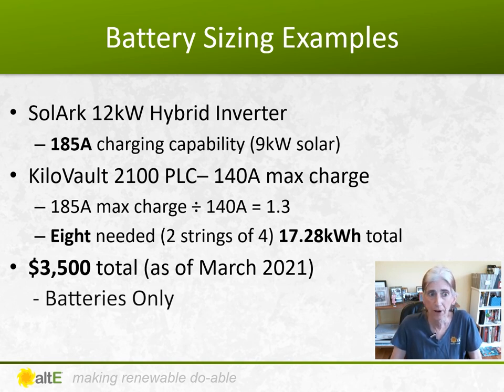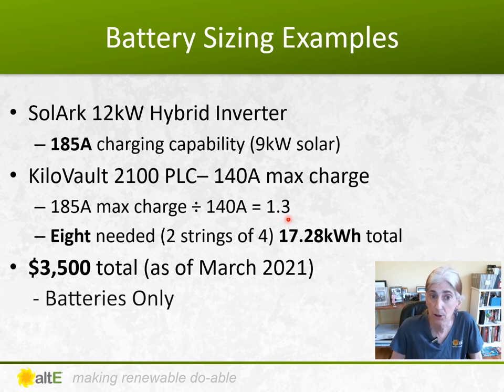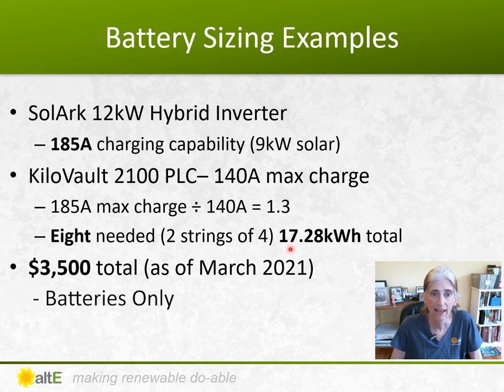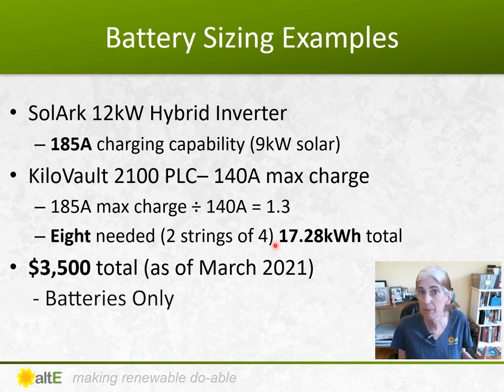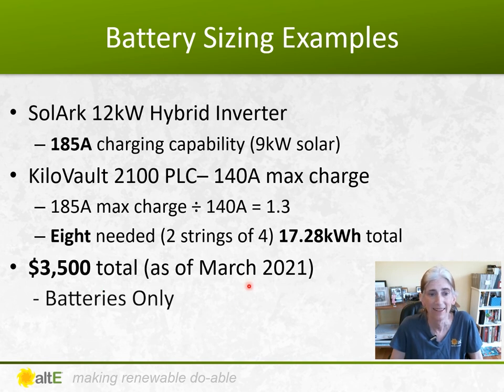Now let's look at the KiloVault 2100 PLC AGM, with a 140 amp maximum charge rate. With 185 amps from solar divided by the recommended 140 amps, that gives 1.3, so we need two strings. Two parallel strings of four batteries in series — only eight batteries total — gives us 17 kilowatt hours. As of March 2021, that's only $3,500 for that battery bank.